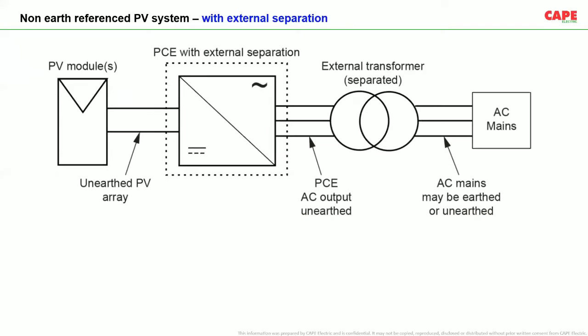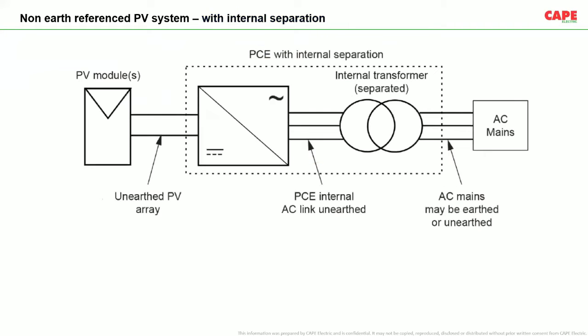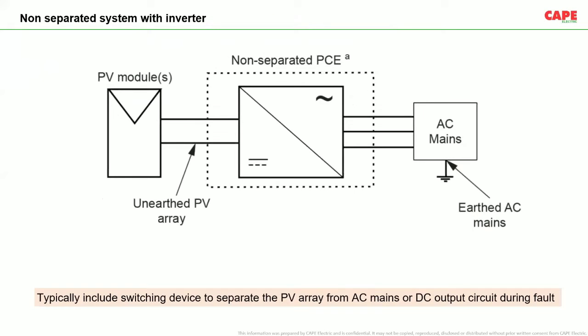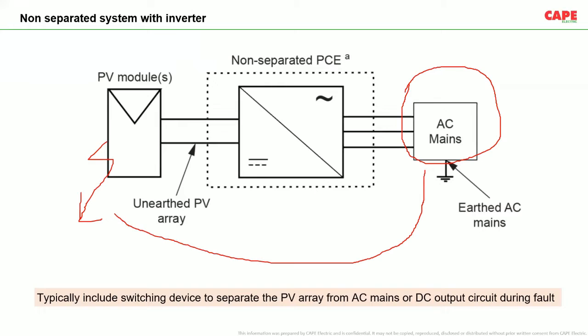Again, non-earth referenced PV system, say for example, here you have a PCE with an external transformer. The same circuit with a PCE with an internal transformer is possible. Then there is the non-separated system with the inverter, where non-separated means the inverter doesn't have any electrical separation between AC and DC. Please try to understand the circuit. There is an AC mains, and the neutral is earthed. Now the PCE doesn't have any electrical separation. That means electrically the PV module and the AC side are connected. Imagine there is an earth fault on the PV side. The fault current will return back to the system through the neutral earthing.